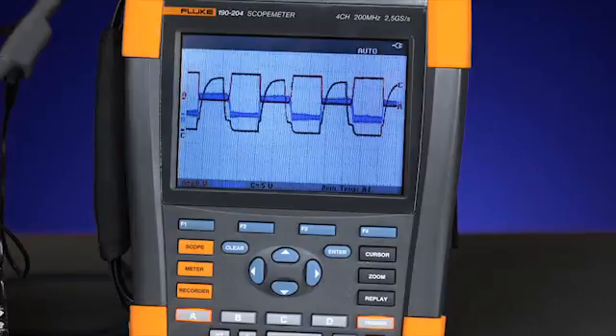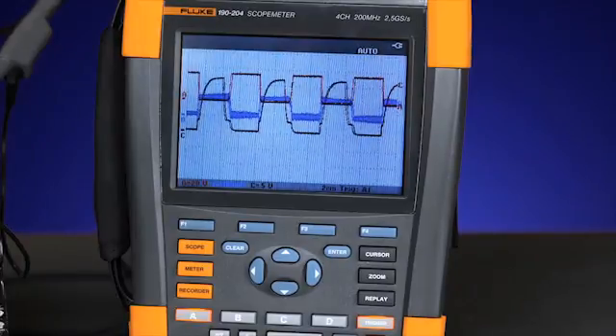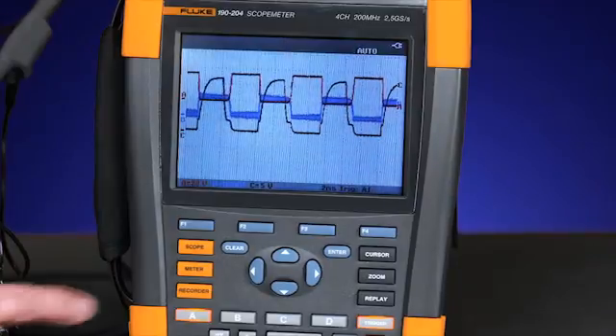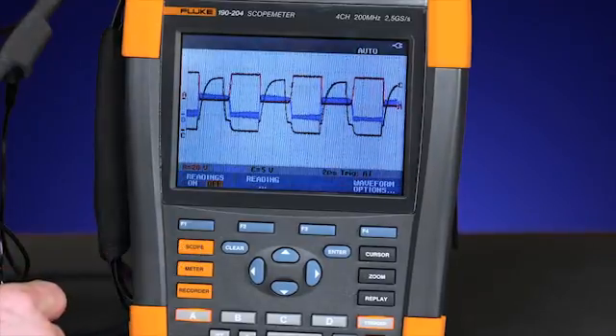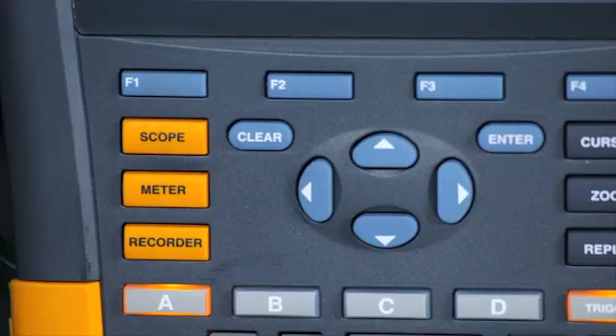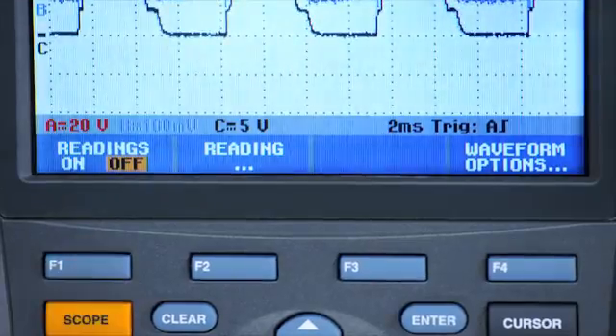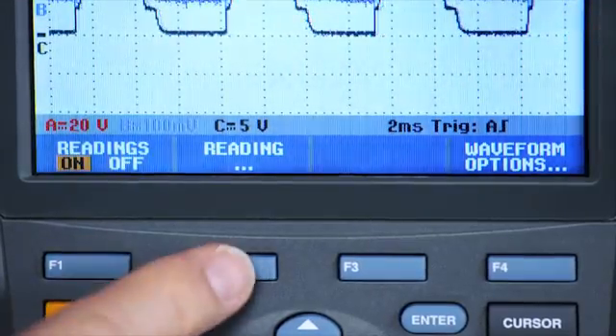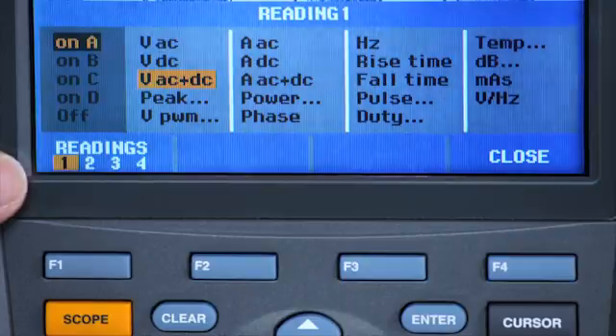For the first measurement, we'll be using the voltage probe on channel A and the current probe on channel B. We'll set up the scope to automatically measure the power across the switch. Press the scope button, then readings on, then choose reading 1 to measure power across A and B.